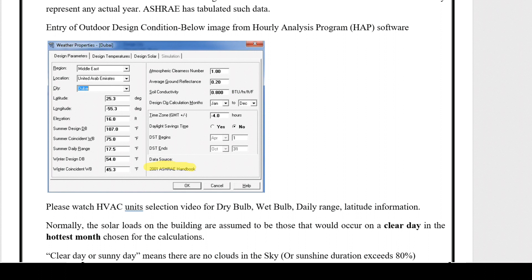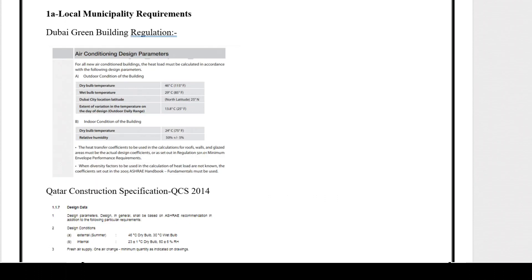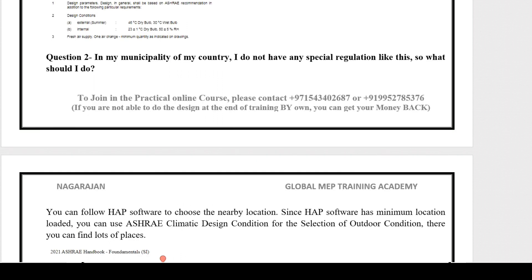If you change any value — for example dry bulb, wet bulb, or daily range — that data source of the 2001 ASHRAE handbook will become 'user modified,' so always notice that point. Normally, solar loads on the building are assumed to be those that would occur on a clear day in the hottest month — a clear, sunny day means there are no clouds in the sky. If your local municipality has special requirements, like Dubai Green Building Regulation or Qatar Construction Specification for dry bulb, wet bulb, latitude, and internal comfort conditions, then you must follow those.